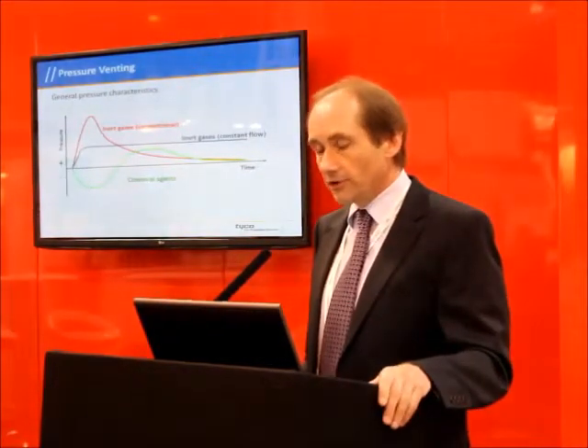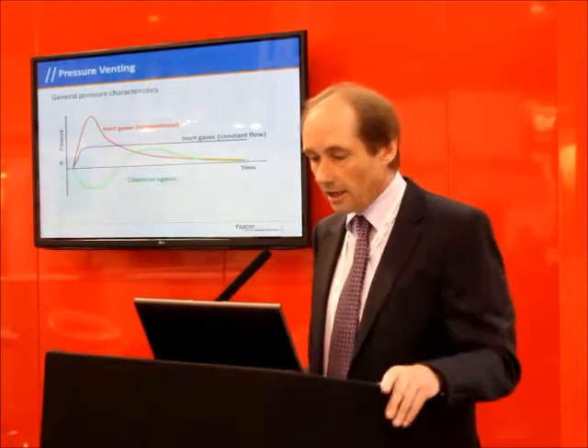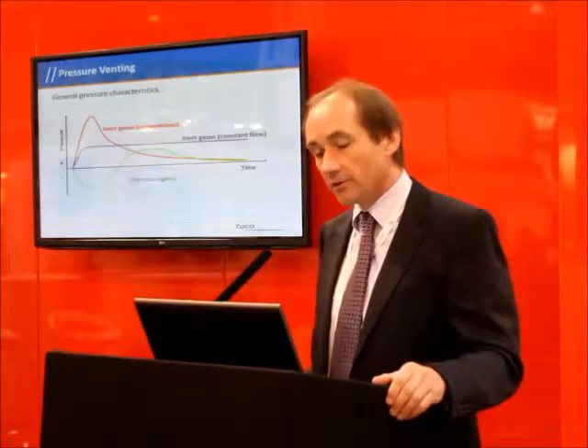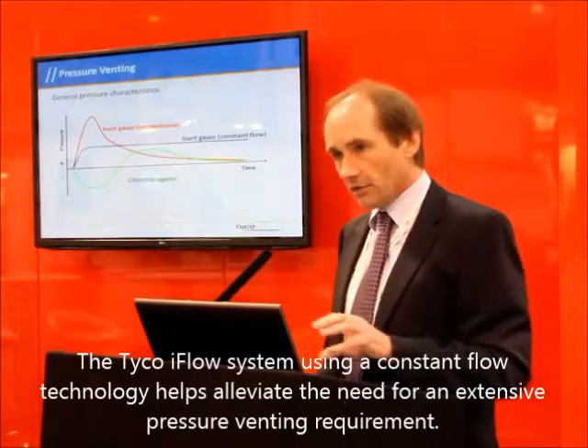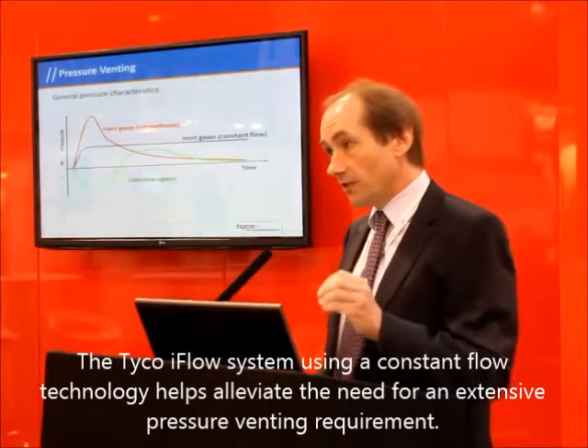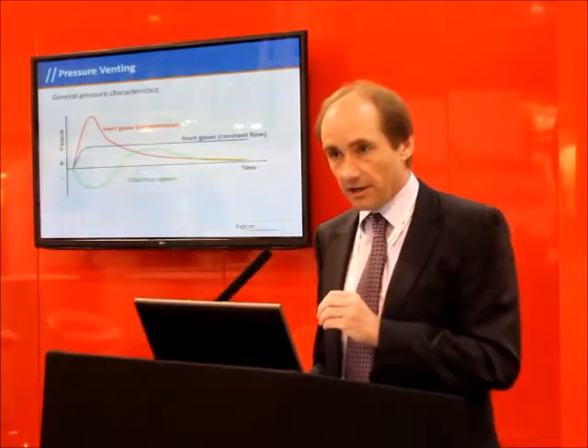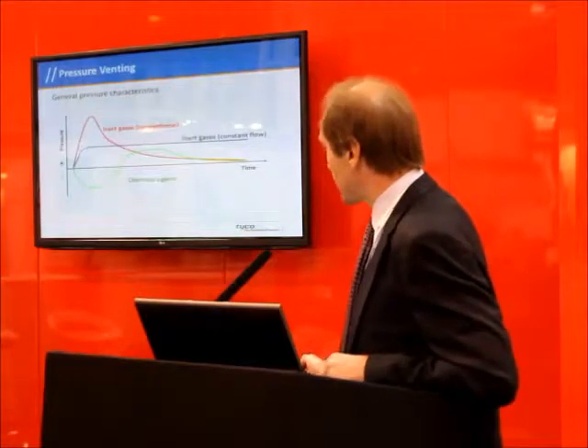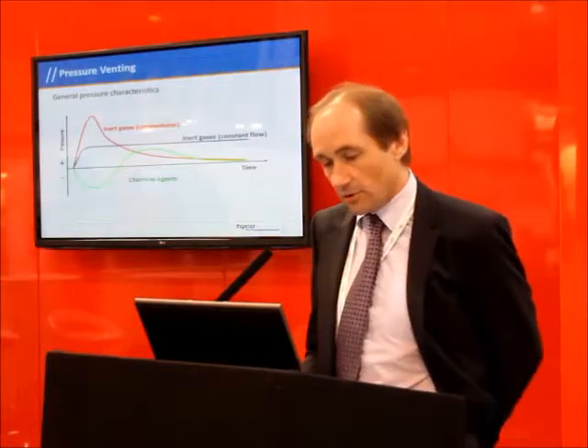The more recent introduction of the inert gas systems, or the constant flow systems — such as the Tyco iFlow system — use what we call a regulated or constant flow technology. What they do is discharge the gas at a constant pressure and a constant flow rate throughout the critical period of the discharge time. That avoids this peak spike and avoids the need to build in such an extensive pressure venting requirement.